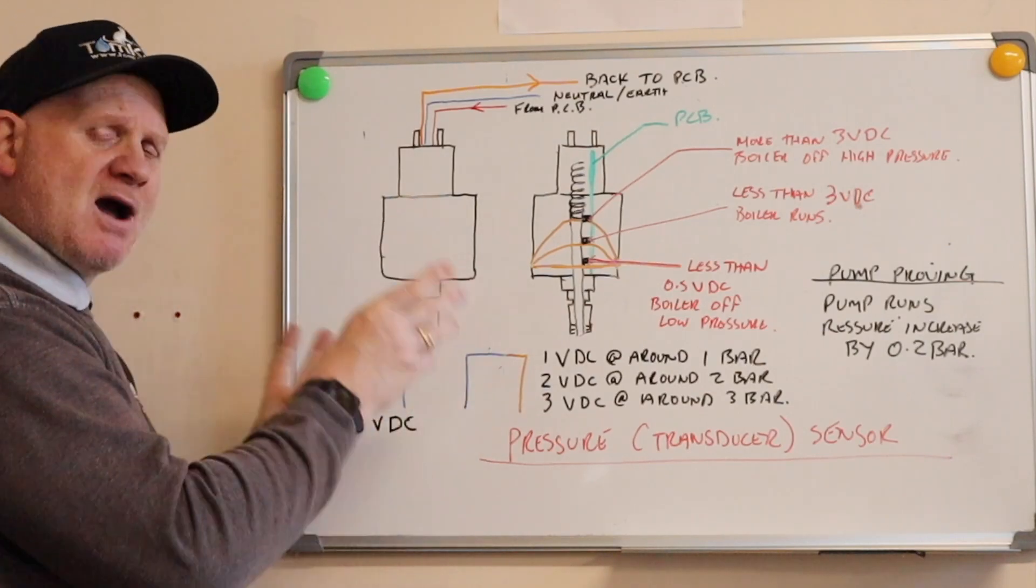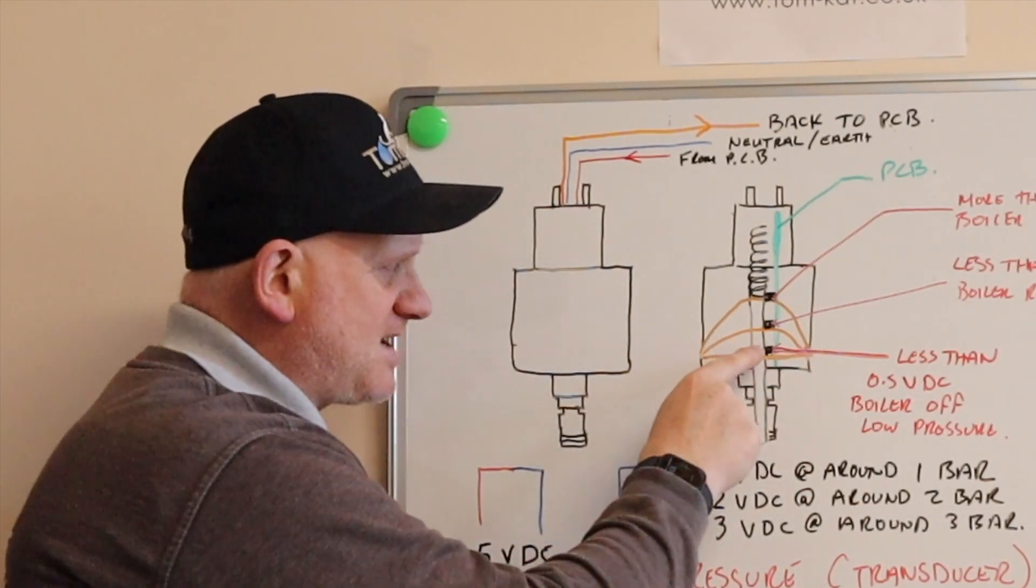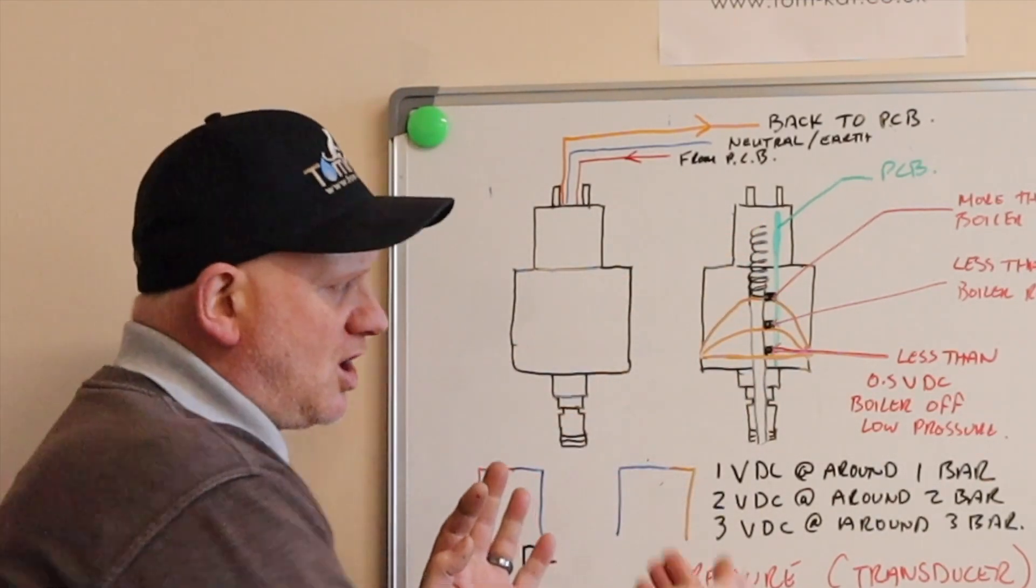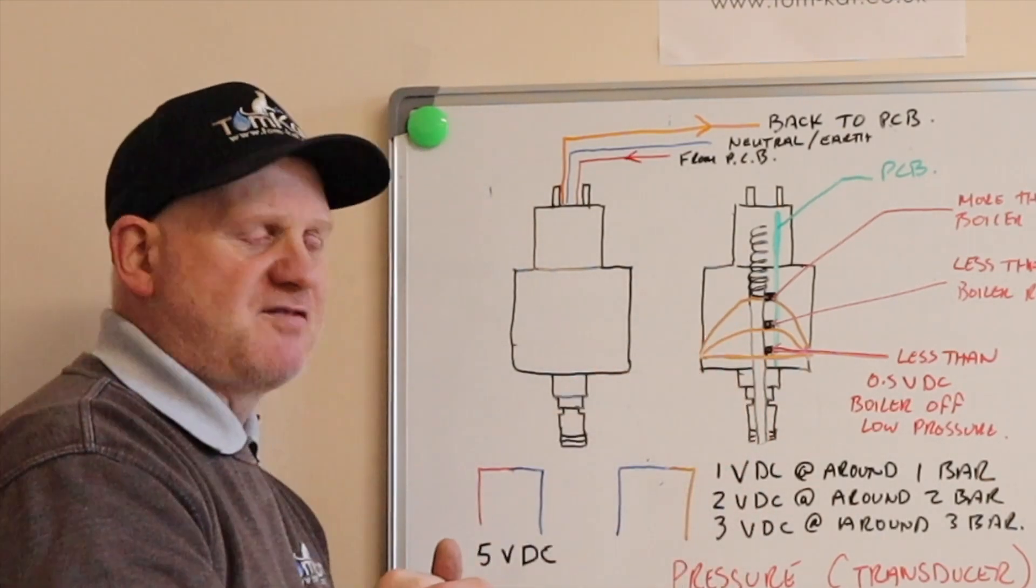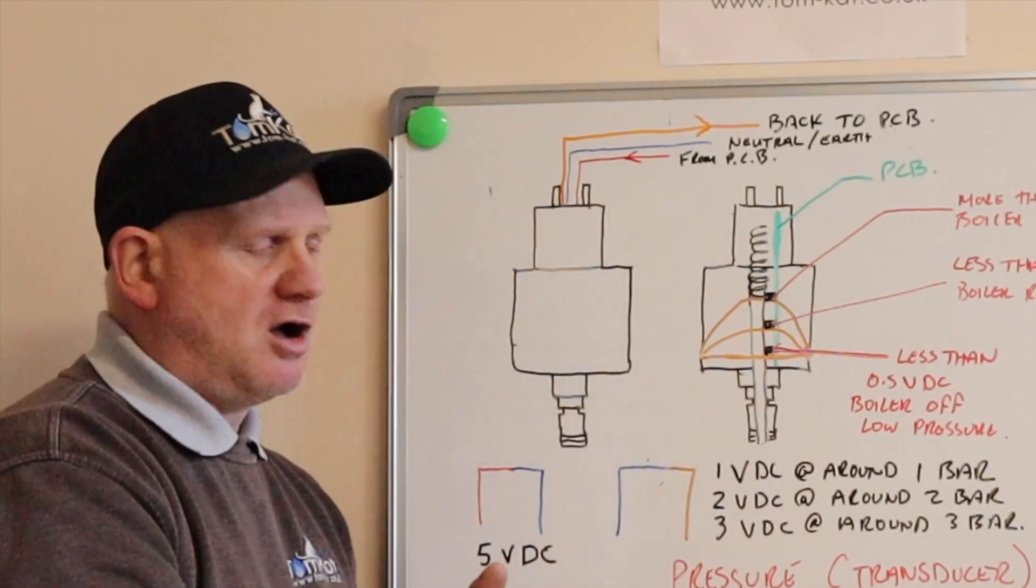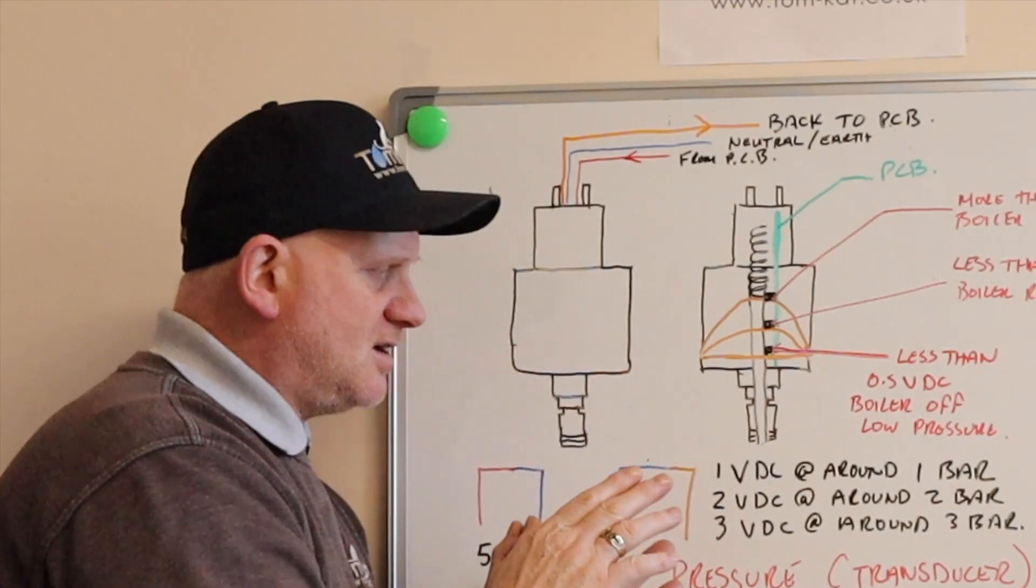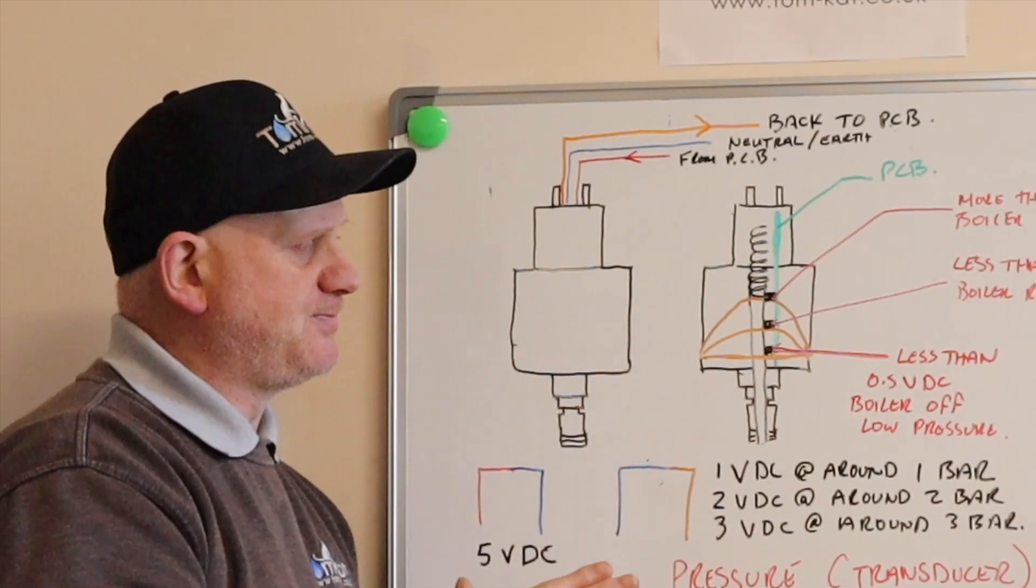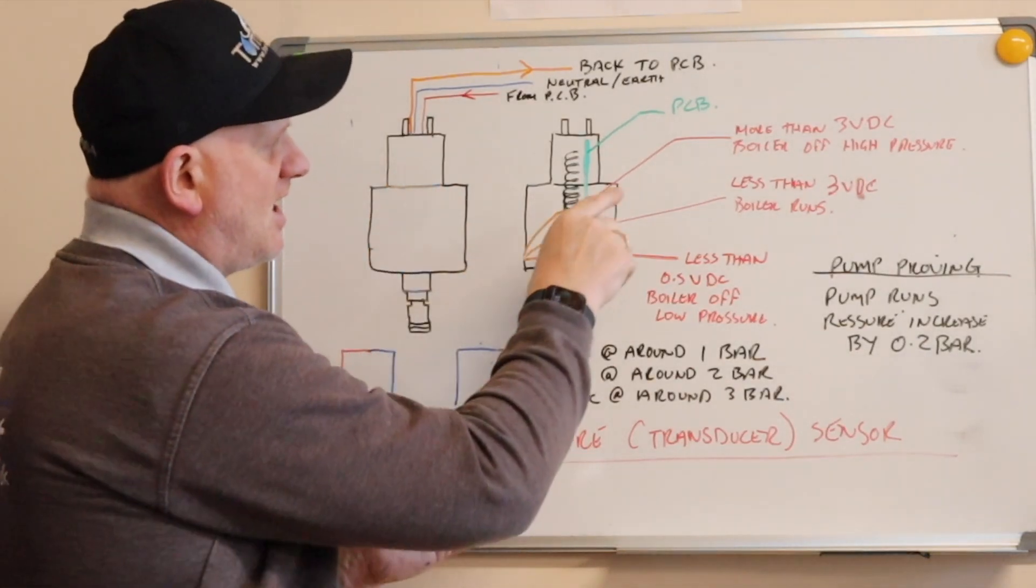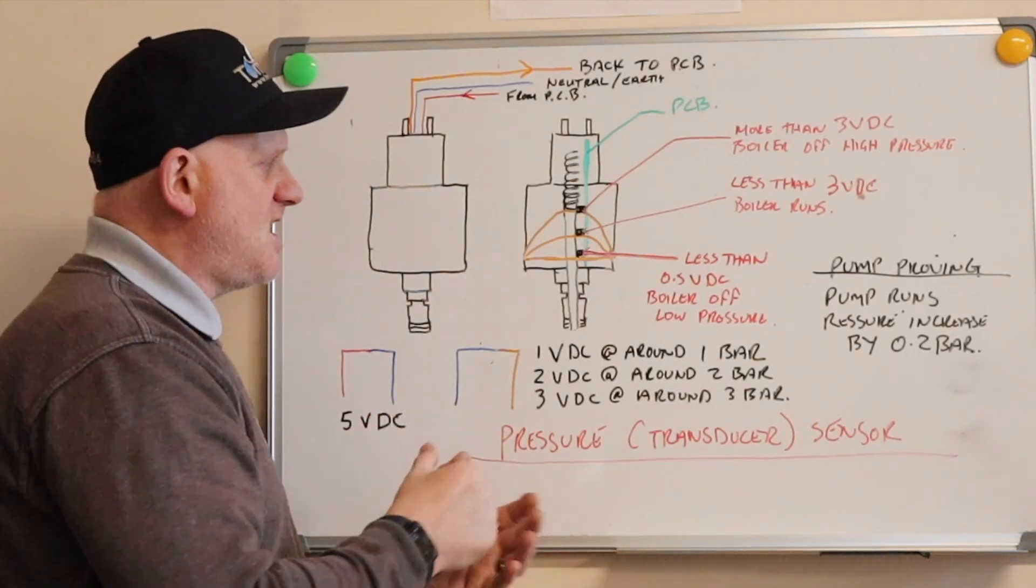So how does it work? If we did a cut-through section, we'll see there is a little diaphragm with a magnet attached to it, there is a PCB, and then a tiny little spring. As the water comes through the hole in the center, it pushes the diaphragm up. So if there's no water, the diaphragm is level, the magnet is down at the bottom of the little PCB inside it, and it's less than 0.5 volts. The boiler knows there's no water in there. As you put the water in there, the magnet will rise up, move up the PCB. If we've got less than 3 bar but more than 0.5 bar or volts DC, then the boiler will run normally.